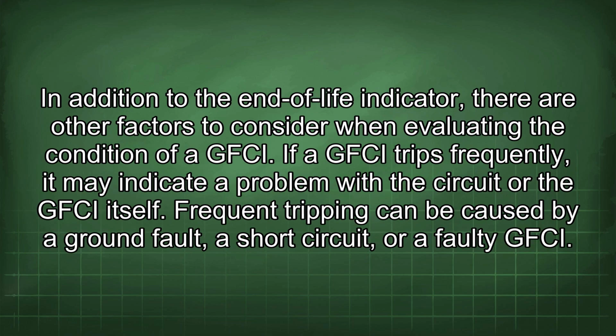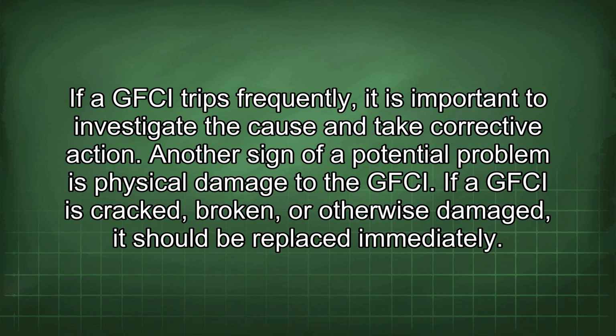In addition to the end-of-life indicator, there are other factors to consider when evaluating the condition of a GFCI. If a GFCI trips frequently, it may indicate a problem with the circuit or the GFCI itself. Frequent tripping can be caused by a ground fault, a short circuit, or a faulty GFCI. If a GFCI trips frequently, it is important to investigate the cause and take corrective action.